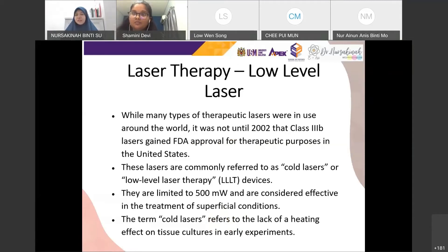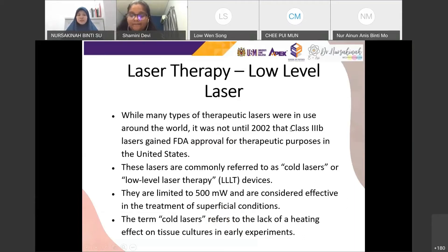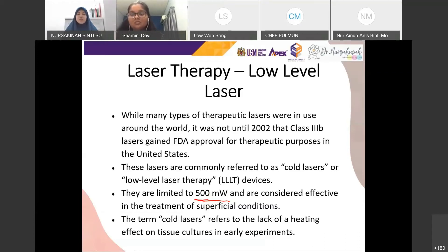How do we classify low-level laser? It was not until 2002 that Class 3B lasers gained FDA approval. These lasers are commonly referred to as cold lasers or low-level laser therapeutic devices. They're called 'cold' because they don't produce thermal effects and are used for therapy. They are limited to only 500 mW — less than 1 W — and are considered effective for treatment of superficial conditions. Cold laser refers to the lack of heating effect on tissue in lab experiments.